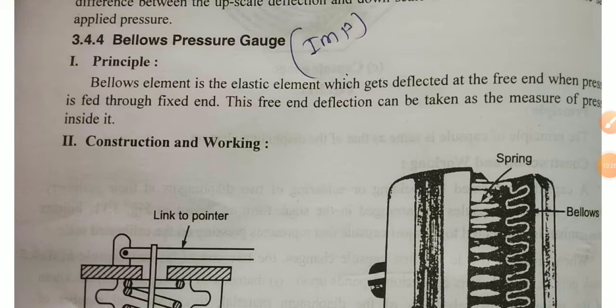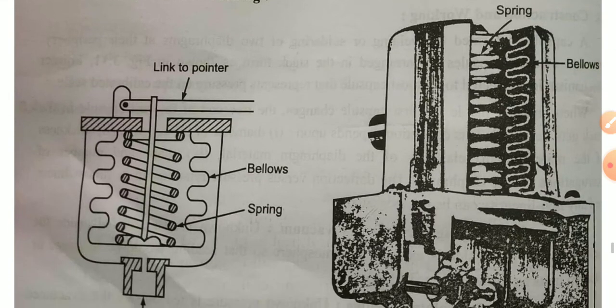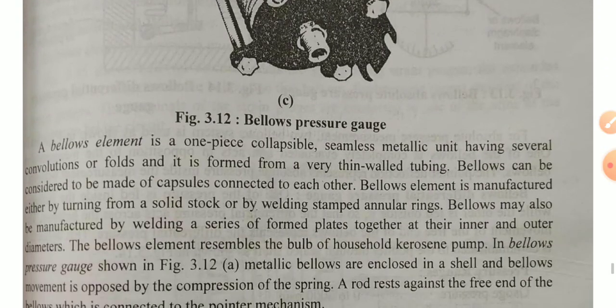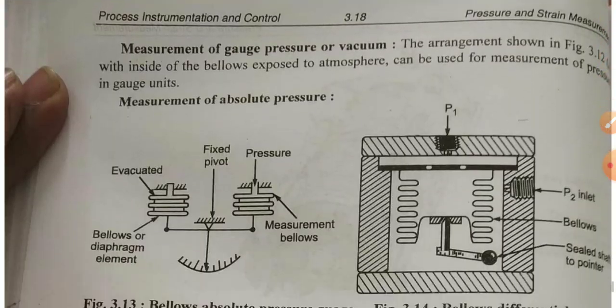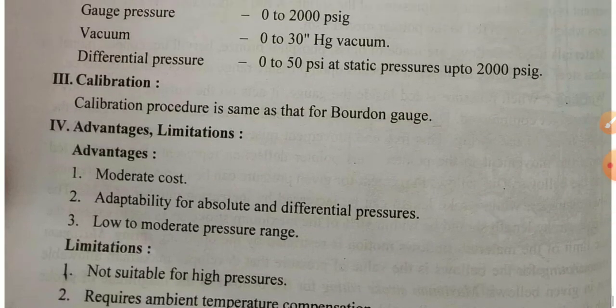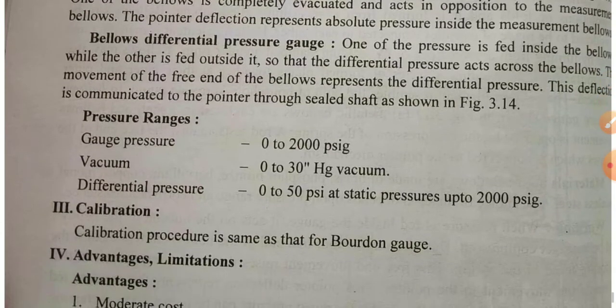This element is an elastic element which gets deflected at the free end when pressure is fed through the fixed end, and this free end deflection can be taken as the measure of the pressure inside it. Now, the construction and working are simple, look at them once in the book. Okay, and the most important is the bellows differential pressure gauge discussion, so let's look at that.